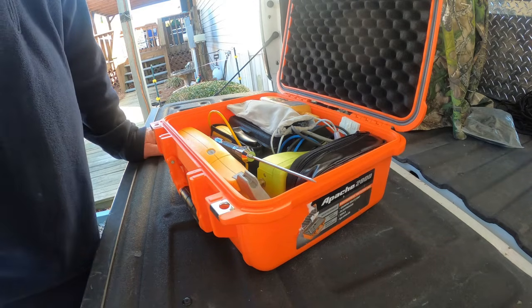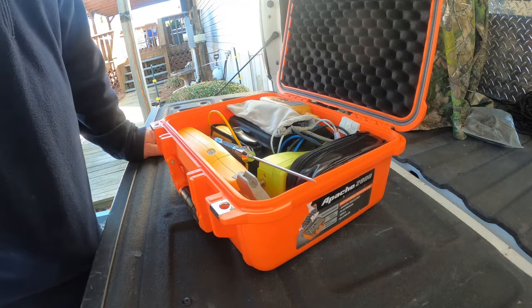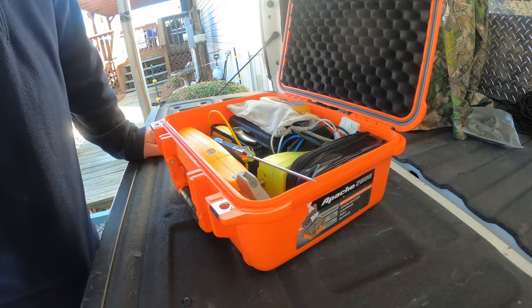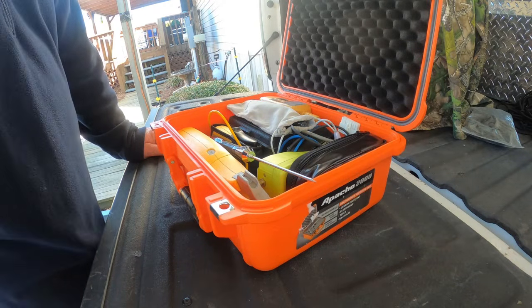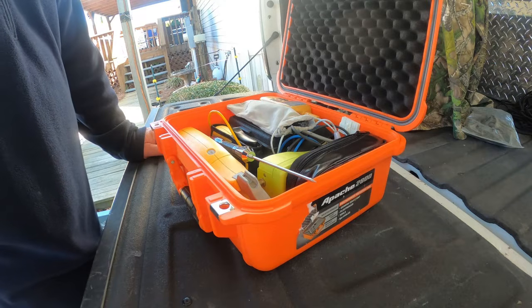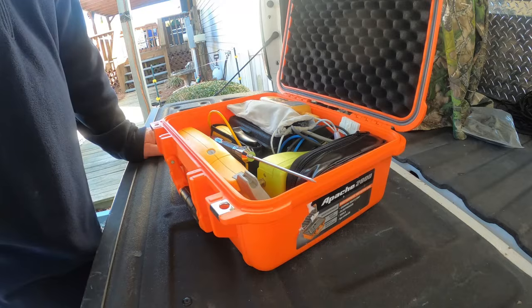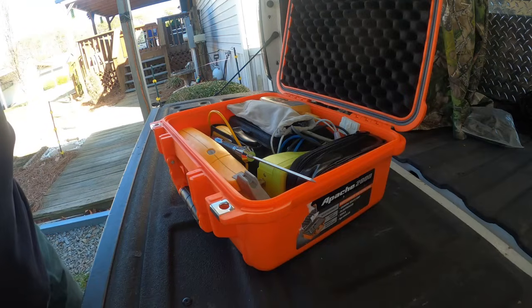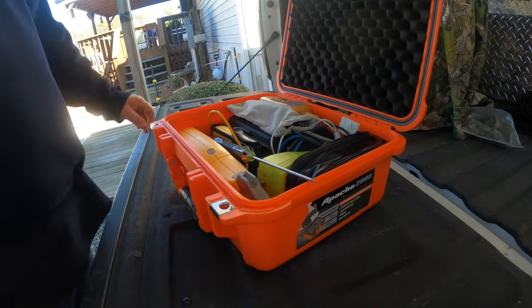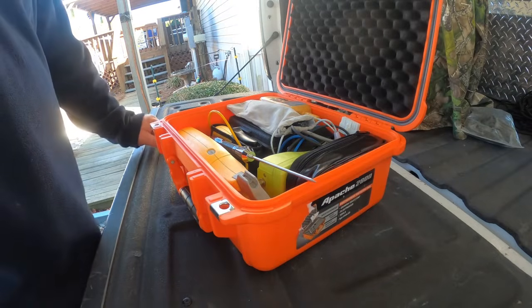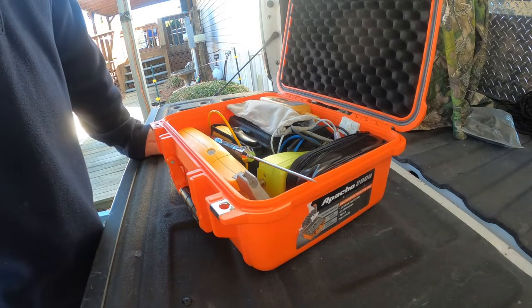So airflow restrictions on a PSC motor, basically your amps are going to drop and your airflow is going to drop. They're not designed to overcome airflow restrictions. So if you've got a dirty filter, maybe you've got a partially collapsed return duct, it'll spin faster, but there's not any air available, and that's why it's going to spin faster. It's going to ramp up, but it's not going to produce any extra CFMs.